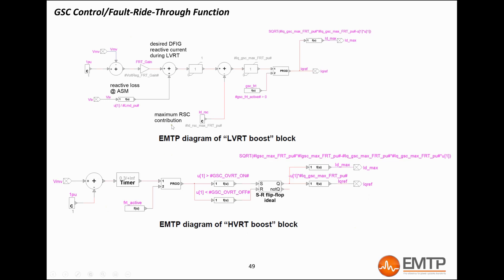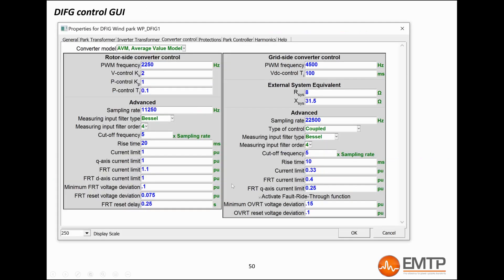During LVRT, the grid-side converter does not contribute before the maximum rotor-side contribution is reached. Then, it starts contributing with a proportional controller. The HVRT, also called OVRT like over voltage ride-through, is activated when the voltage goes above a certain threshold. All the FRT threshold can be found in the converter control data tab, as well as the parameters required by the inner and outer control loops.